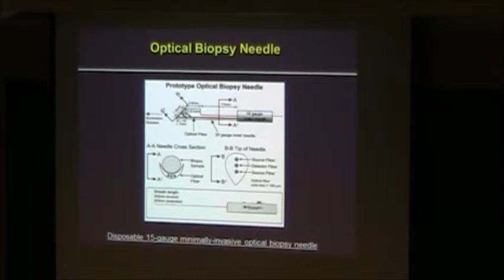They went through and came up with drawings, and then they came up with several configurations, 6x1 and 8x1 fiber configurations for the probe, and of course they did some ray tracing. Now the challenge was, it's a needle, so it has to be cut at an angle. Why is this so critical? If it is a flat probe, everything coming from the fiber will come out of the probe. By Snell's law, if it's an angle, light begins to bend. Especially coming from fiber, where the refractive index is glass into air, some of it is going to be reflected back. So the angle is very critical.